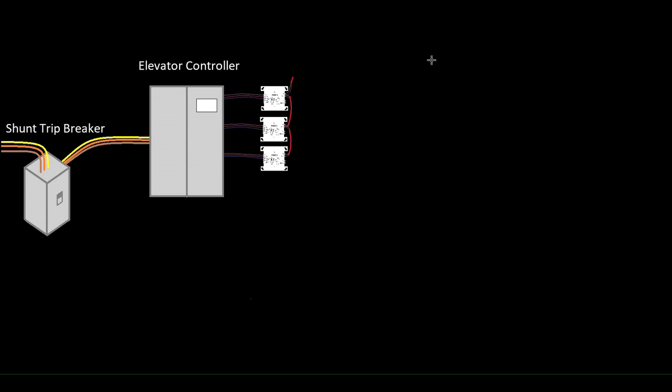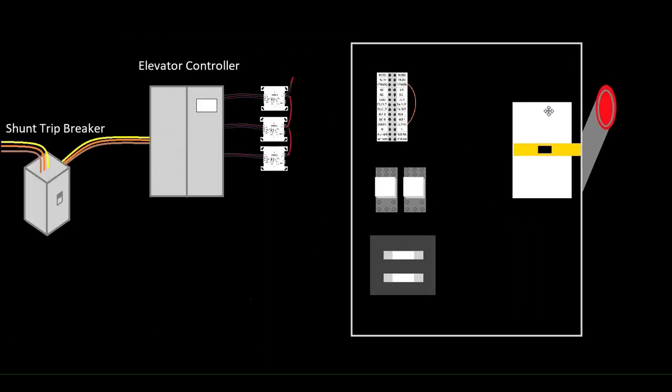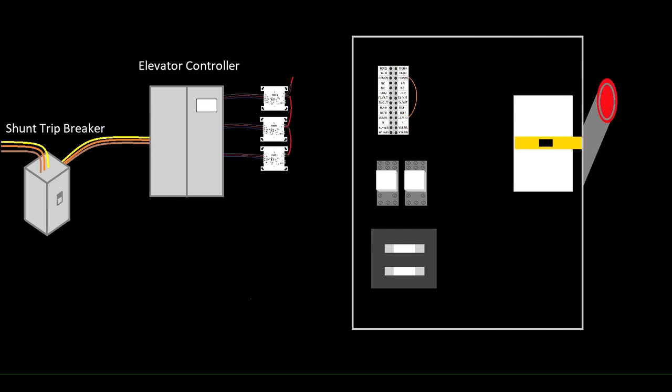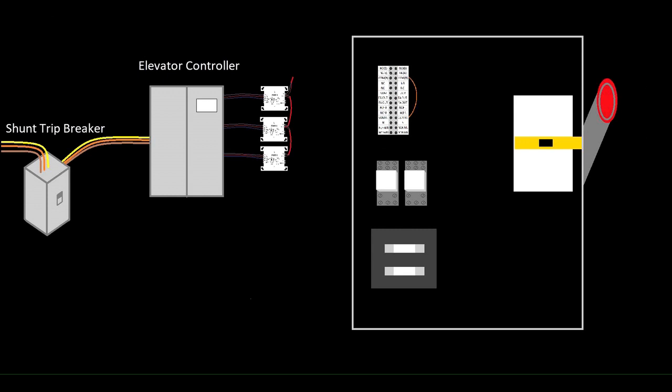I'm going to bring in my representation of that shunt trip breaker opened up. So this big red handle on the right would be the disconnect. What we have here is a terminal block up here which we'll look at in more detail in a second, and that terminal block has a bunch of factory wiring going down to these two cube relays here. The cube relays take the place of, among other things, our two MR-101s that we had in the last video, and so that's why we don't need those anymore.